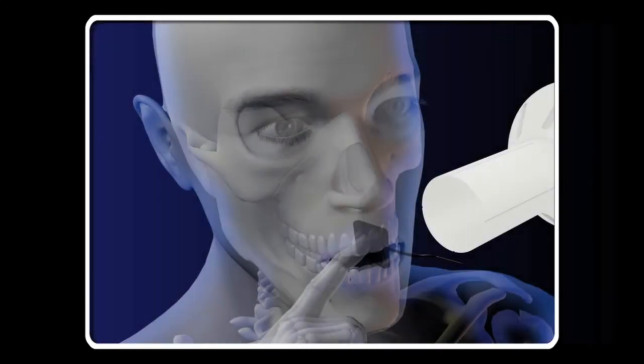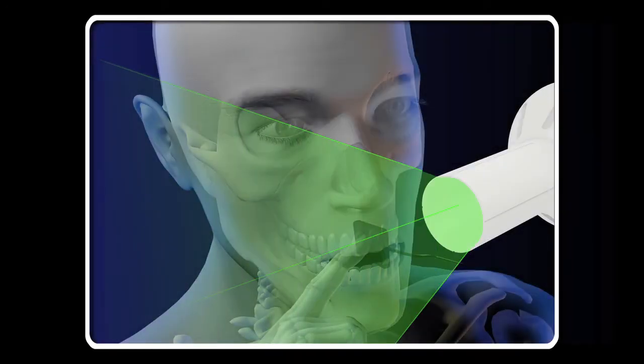A round cone acts like a shotgun as radiation exits the cone in a spreading pattern. Only about 10% of the beam actually hits the receptor. Many photons are scattered into the patient's tissues or reflected back onto the receptor as noise or fog, compromising the image resolution and diminishing the diagnostic quality.